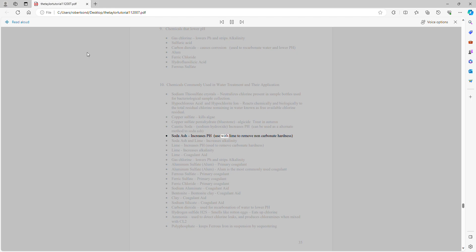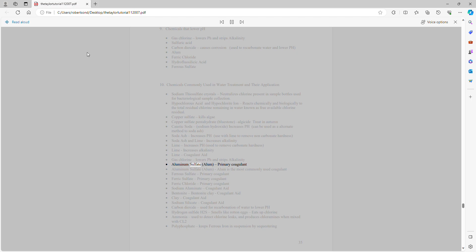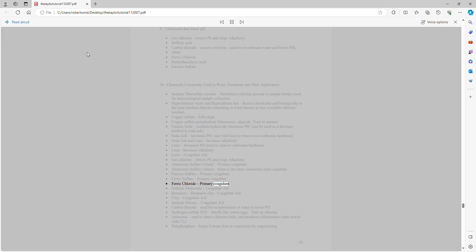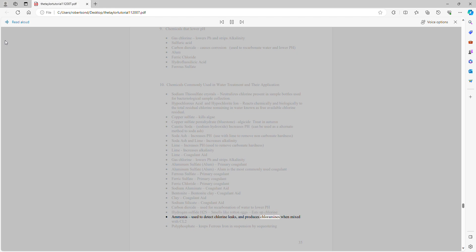Soda ash increases pH and is used with lime to remove non-carbonate hardness. Lime increases pH and is used to remove carbonate hardness; also increases alkalinity. Gas chlorine lowers pH and strips alkalinity. Aluminum sulfate (alum) is the most commonly used coagulant. Ferrous sulfate, ferric sulfate, and ferric chloride are primary coagulants. Sodium aluminate, bentonite clay, and sodium silicate are coagulant aids. Carbon dioxide is used for recarbonation to lower pH. Hydrogen sulfide (H₂S) smells like rotten eggs and consumes chlorine. Ammonia is used to detect chlorine leaks and produces chloramines when mixed with Cl₂. Polyphosphate keeps ferrous iron in suspension by sequestering.